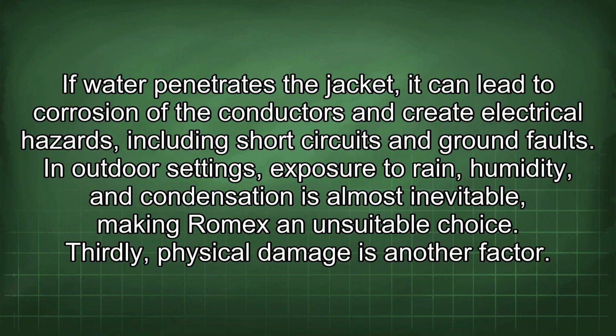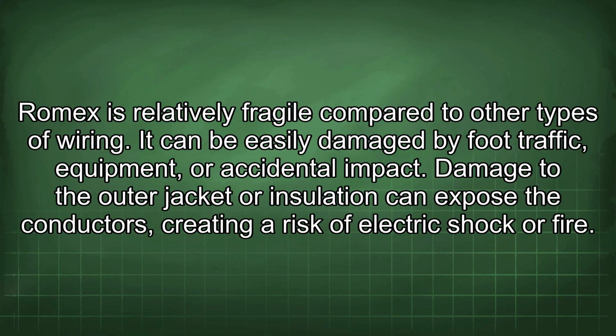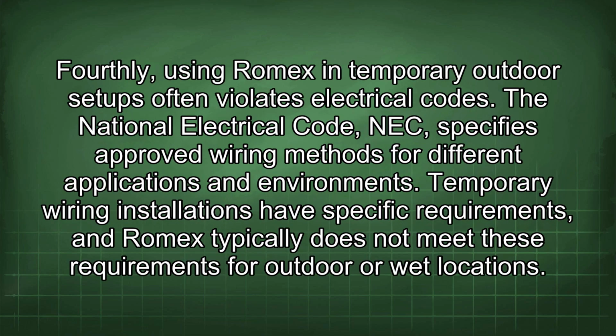Thirdly, physical damage is another factor. Romex is relatively fragile compared to other types of wiring. It can be easily damaged by foot traffic, equipment, or accidental impact. Damage to the outer jacket or insulation can expose the conductors, creating a risk of electric shock or fire. Fourthly, using Romex in temporary outdoor setups often violates electrical codes. The National Electrical Code (NEC) specifies approved wiring methods for different applications and environments. Temporary wiring installations have specific requirements, and Romex typically does not meet these requirements for outdoor or wet locations.